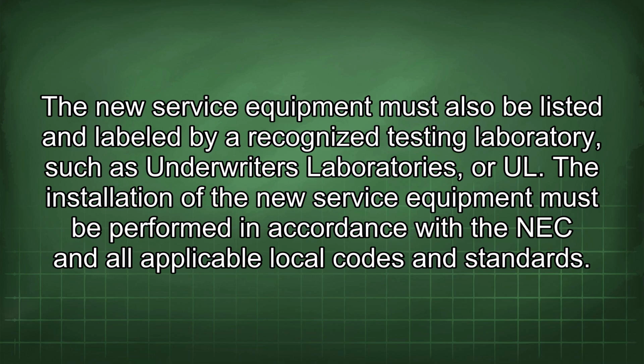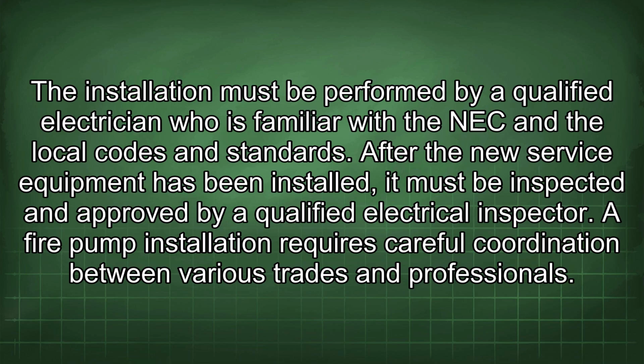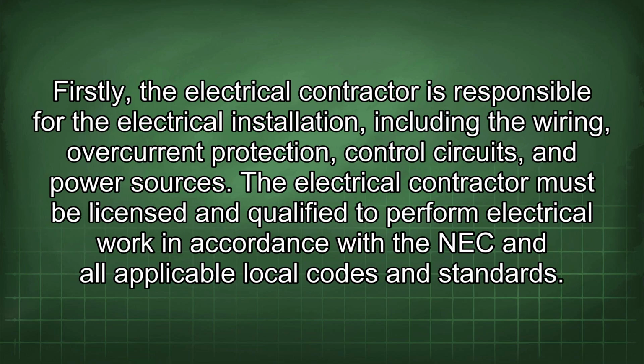The installation must be performed by a qualified electrician who is familiar with the NEC and the local codes and standards. After the new service equipment has been installed, it must be inspected and approved by a qualified electrical inspector. A fire pump installation requires careful coordination between various trades and professionals. Firstly, the electrical contractor is responsible for the electrical installation, including the wiring, overcurrent protection, control circuits, and power sources. The electrical contractor must be licensed and qualified to perform electrical work in accordance with the NEC and all applicable local codes and standards.